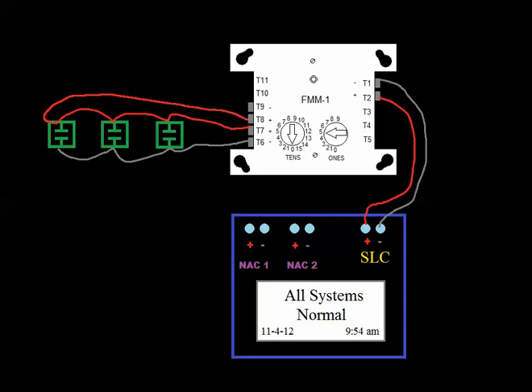Now, I have personally never seen a monitor module hooked up as a class A. I've seen conventional panels that have class A circuits. You know, you see that quite a bit, but a monitor module, you do have the capability of hooking it up this way, although, like I said, I've never seen it. And in this case, when you do that, you put your resistor right here at terminals 8 and 9.